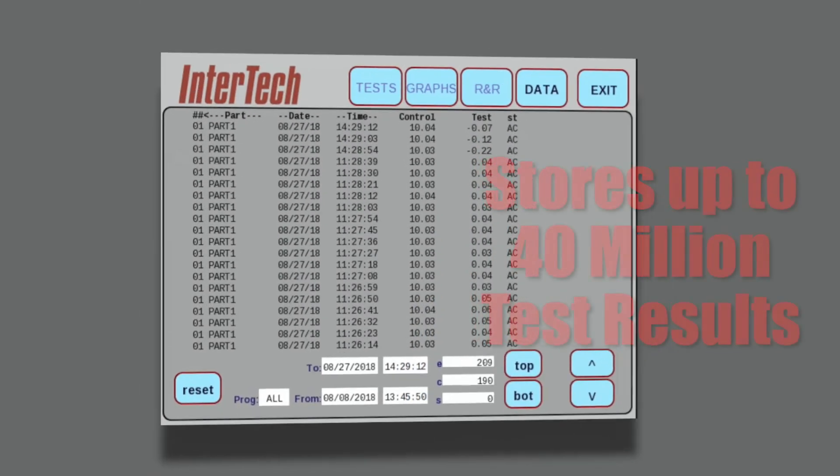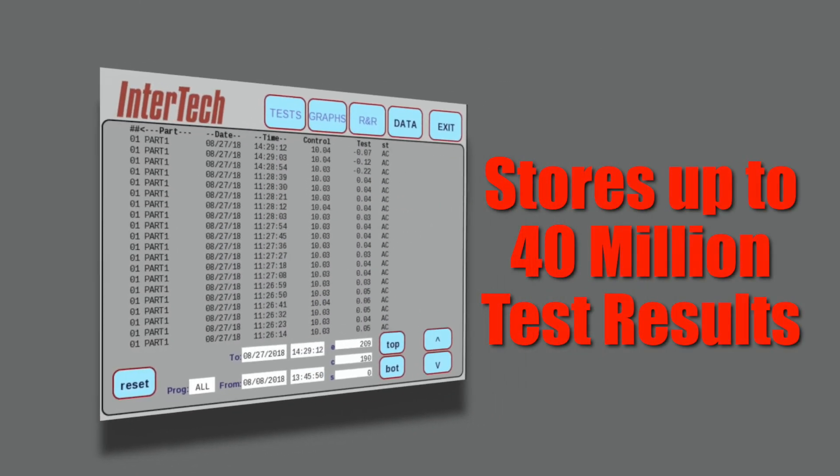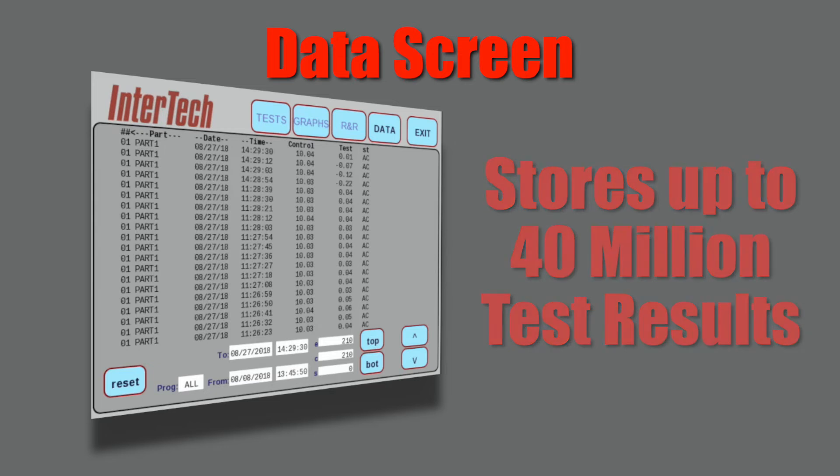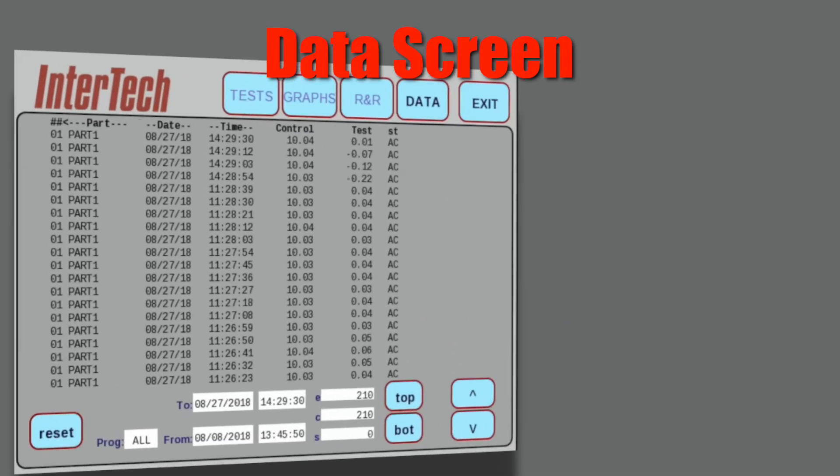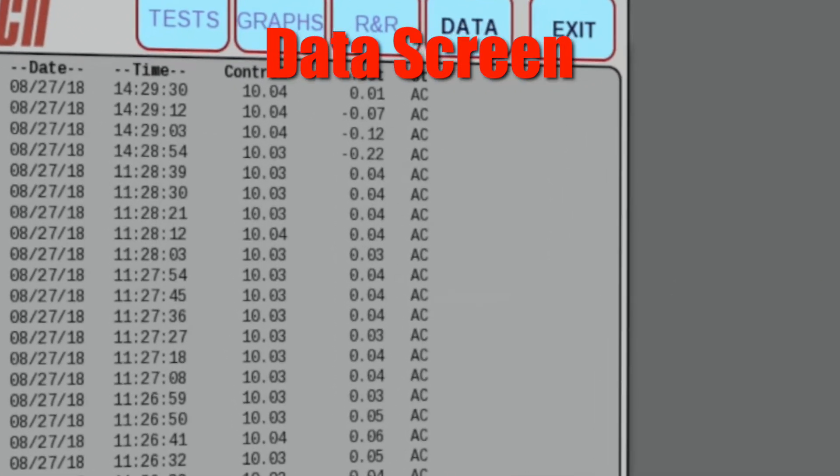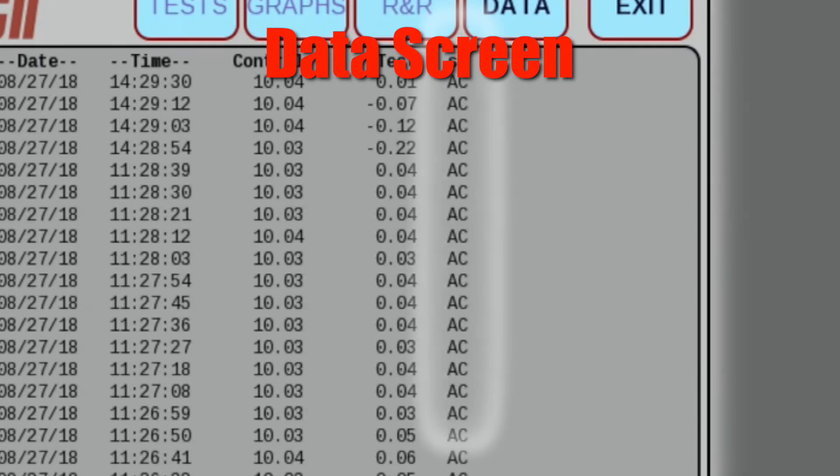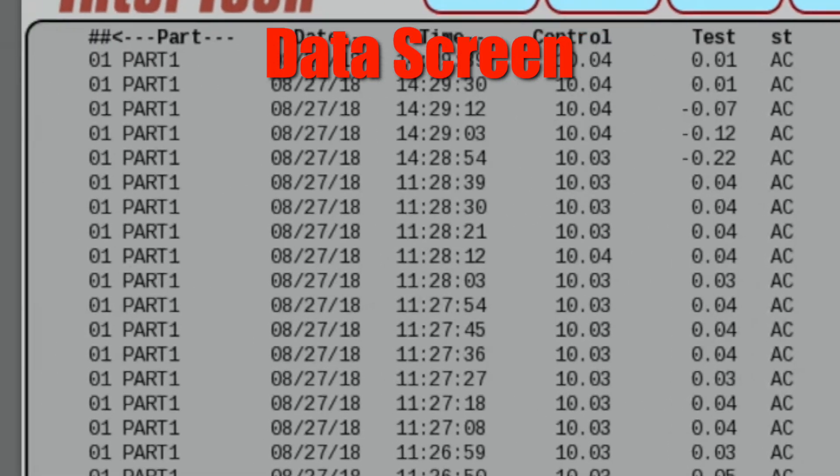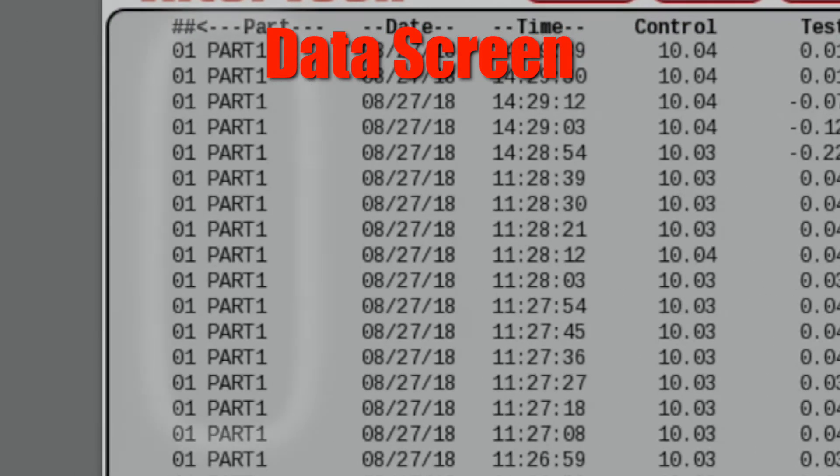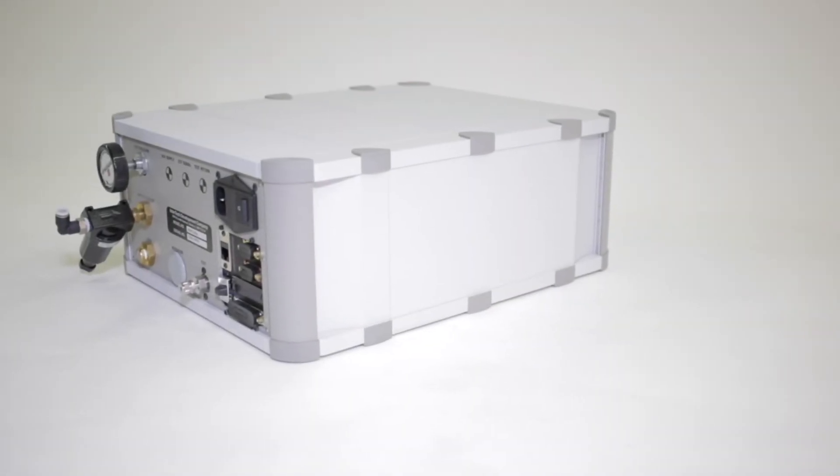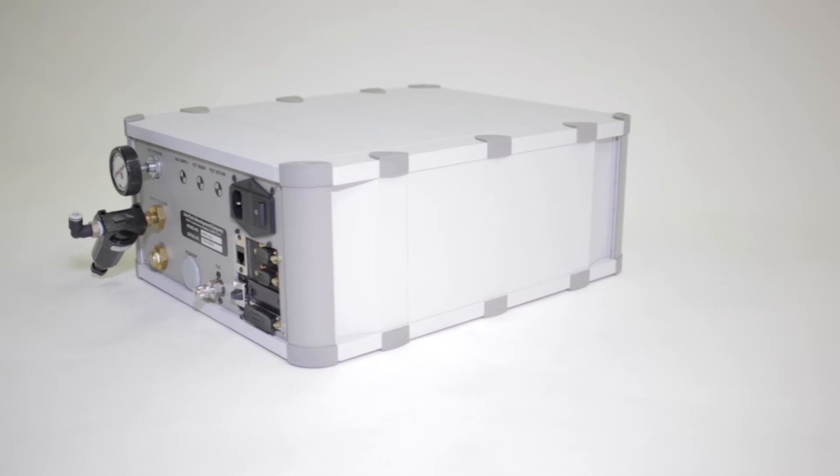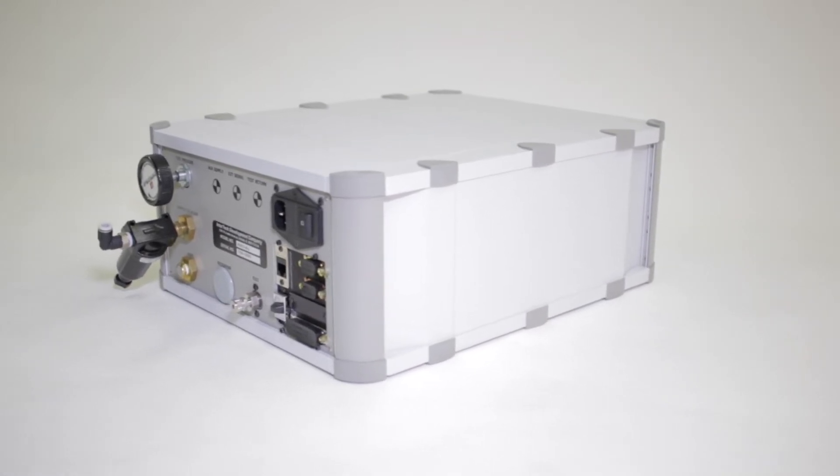The M1075 stores up to 40 million test results. Date and time ranges can be set for downloading to an Excel file using a USB stick via the USB port on the front. A two-letter code is provided at the end of the cycle to define the test result condition. When incorporating a barcode reader, the part number can be exchanged for a part serial number in the database.